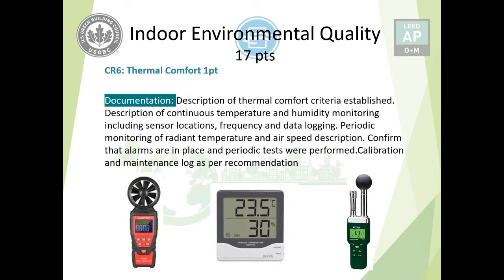For documentation, the handheld devices shown include one for mean radiant temperature, one for airspeed, and a digital sensor for temperature and humidity. Documentation must include the thermal comfort criteria established, continuous temperature and humidity monitoring with sensor locations on drawings, frequency of data collection and logging, periodic monitoring of temperature and airspeed, alarm procedures and SOPs, and a calibration and maintenance log per manufacturer recommendation.